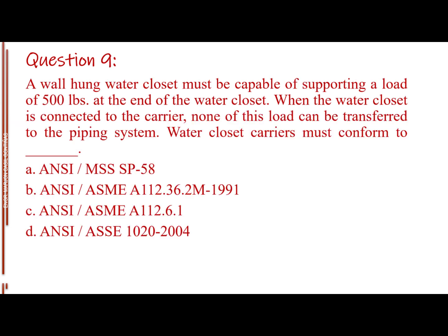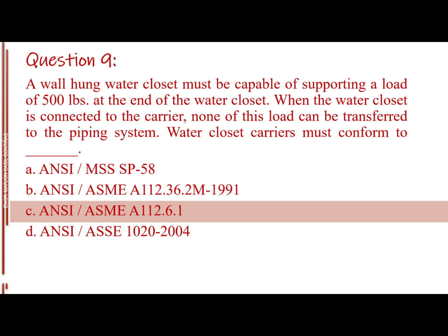Question number 9. A wall-hung water closet must be capable of supporting a load of 500 pounds at the end of the water closet. When the water closet is connected to the carrier, none of this load can be transferred to the piping system. Water closet carriers must conform to blank. Letter A, ANSI MSS SP 58. Letter B, ANSI ASME A112.36.2M 1991. Letter C, ANSI ASME A112.6.1. Letter D, ANSI ASSE 1020-2004. The answer is Letter C, ANSI ASME A112.6.1.